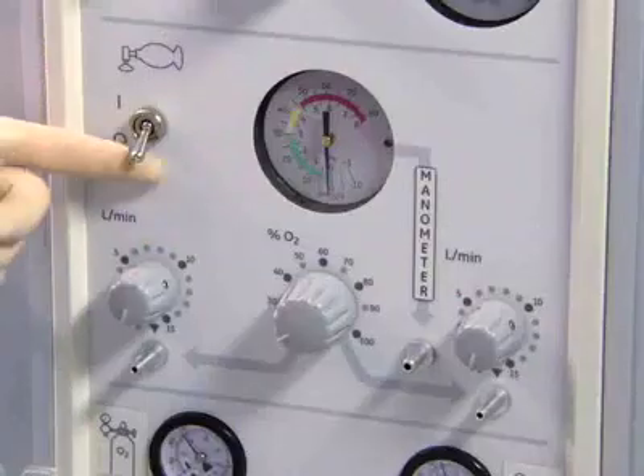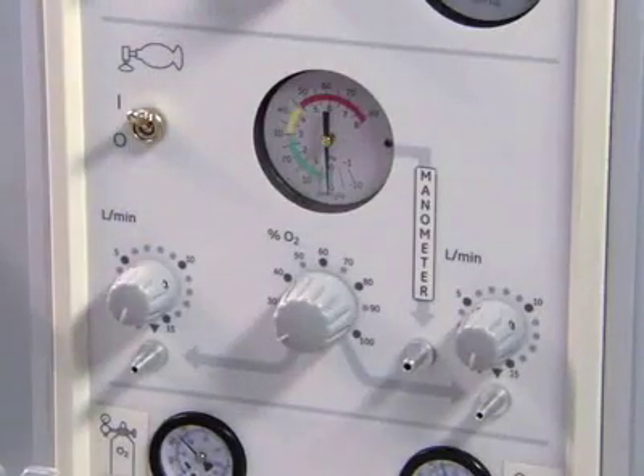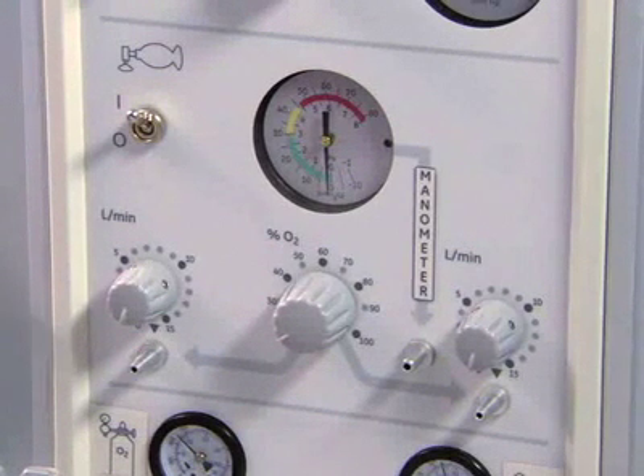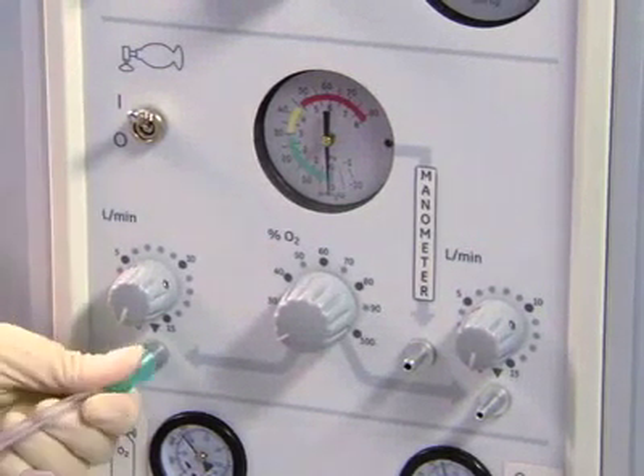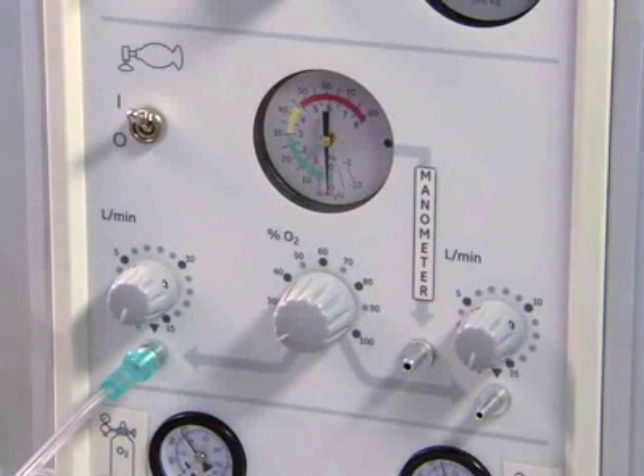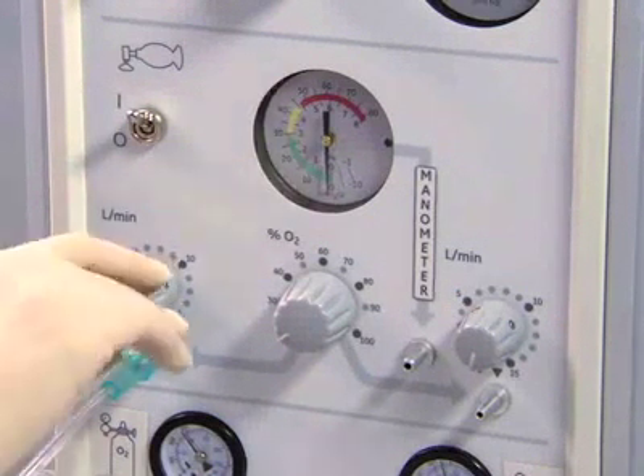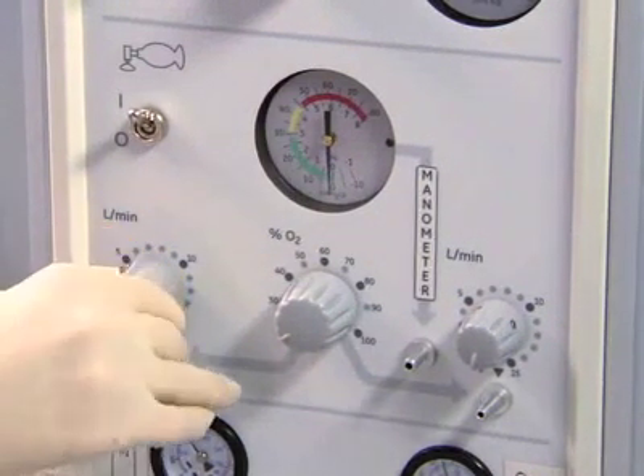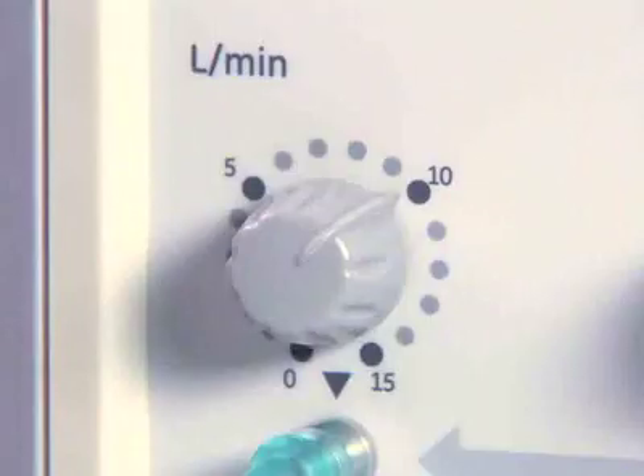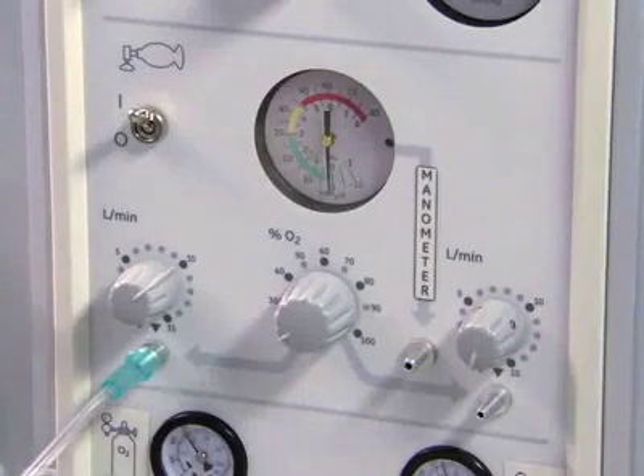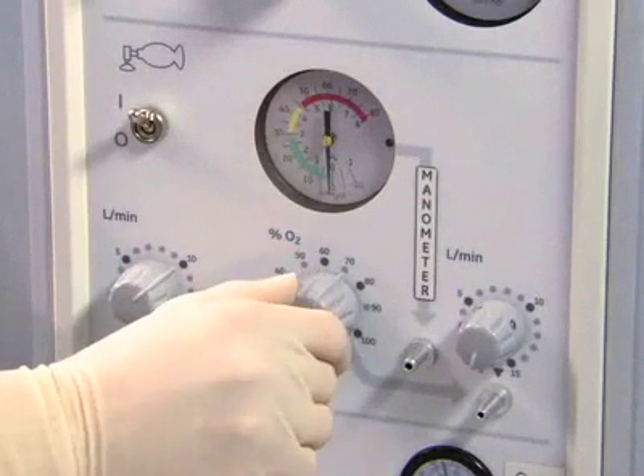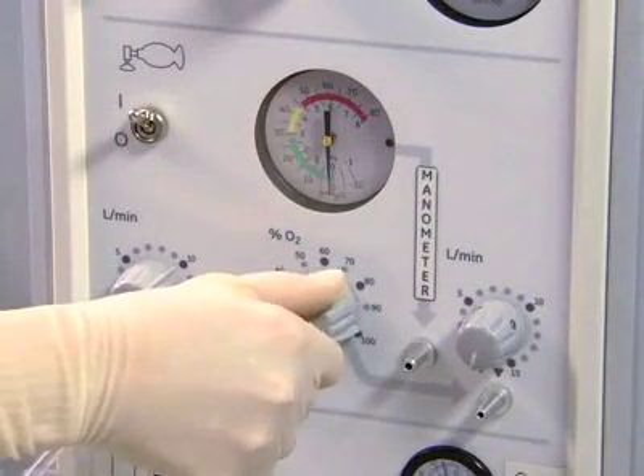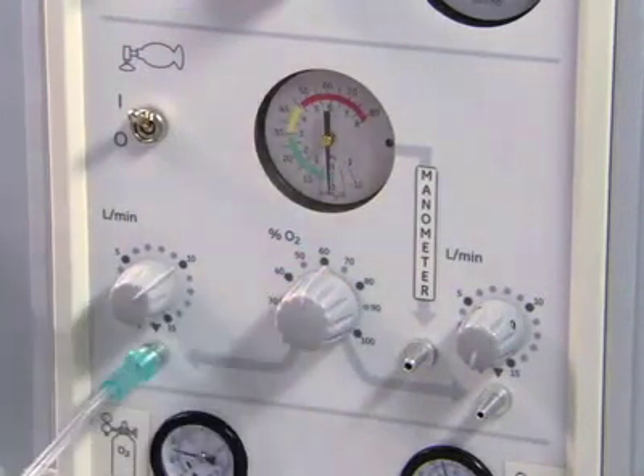Turn the medical gas switch on. Attach oxygen connecting tubing for free flow oxygen to the left gas outlet on the front panel of the resuscitation system, and adjust the flow meter control knob above the outlet to a desired flow rate between 5 and 15 liters per minute. 10 liters per minute is effective in most cases. For units with a blender, adjust the blender control knob to set the desired FiO2 from 21% to 100%.